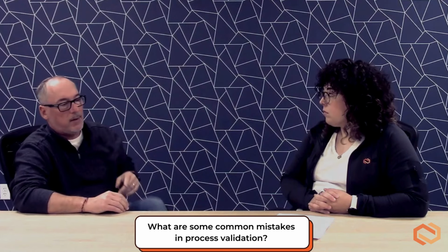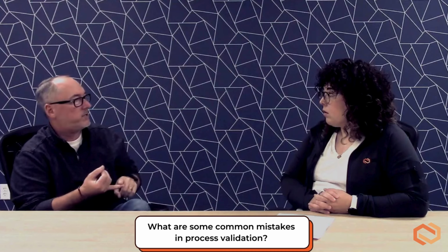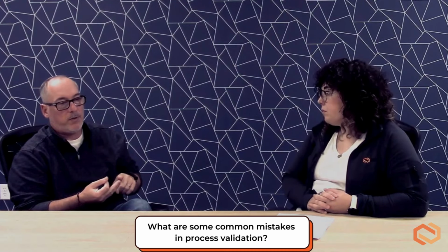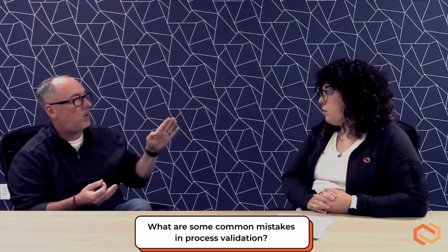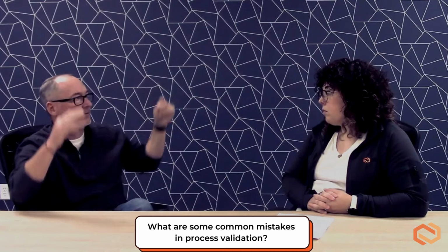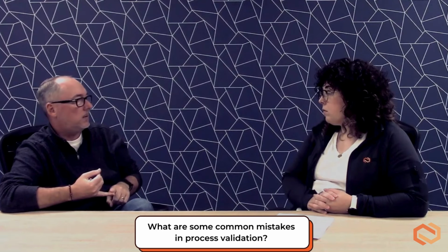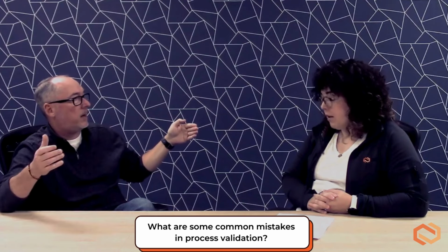Now in saying that, I see a lot of issues with oversealing, undersealing. I see a lot of issues with not understanding the actual processing parameters, your low, your nominal, and your high, basically your processing window. I also see a lot of issues with choosing what strength level to use on your low end or your high end. That's a big one, yeah.